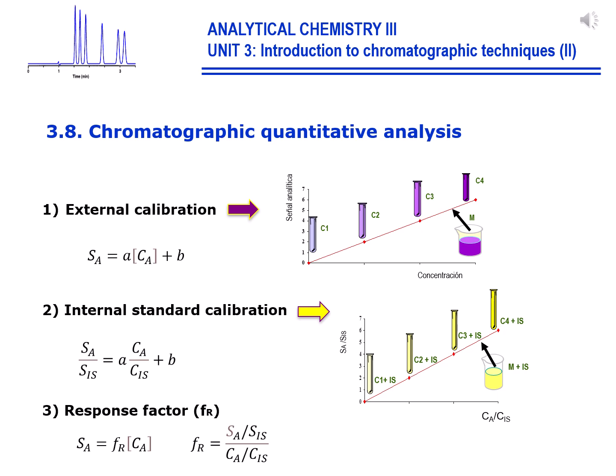Response factor. In this calibration approach, there is no need to plot a calibration curve. Now, peak areas are corrected according to the detector response by dividing the values measured by the response factor for each analyte and the response of the internal standard. For this method, it's mandatory to precisely know the response factor Fr for each analyte with a specific detector. If the detector changes, Fr may change. This quantification mode is widely employed in gas chromatography.